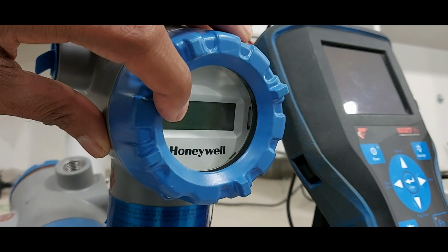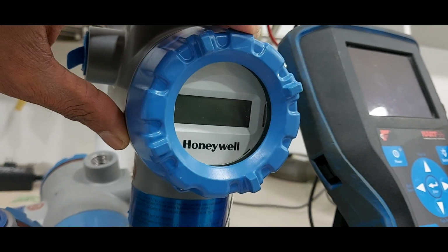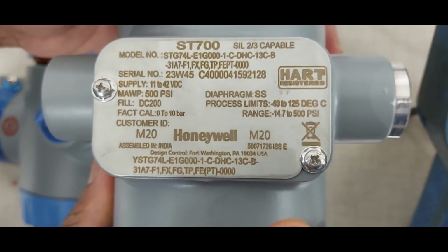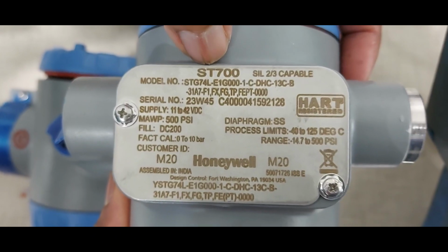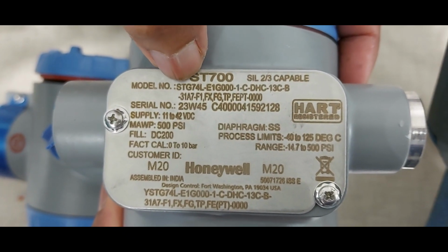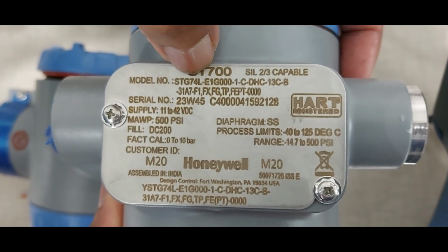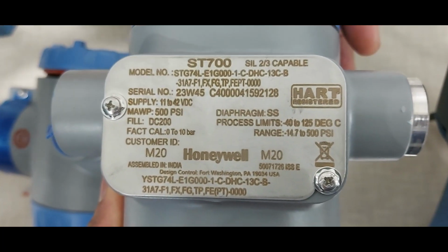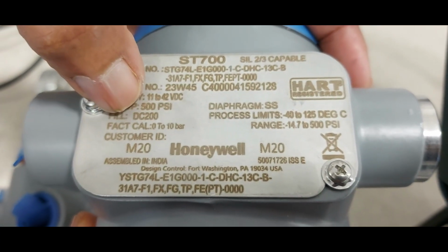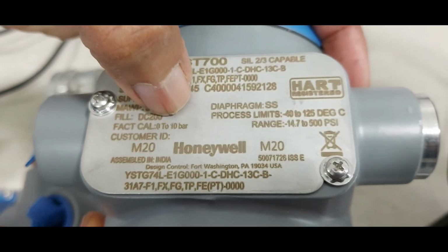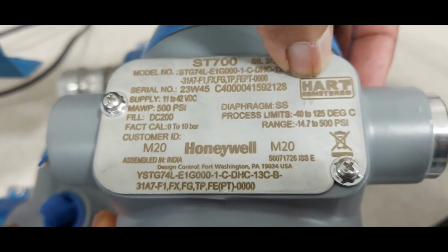Today I am introducing you Honeywell pressure transmitter calibration. Honeywell ST700, STG74L. Instrument calibration range 0 to 10 bar. HART protocol.